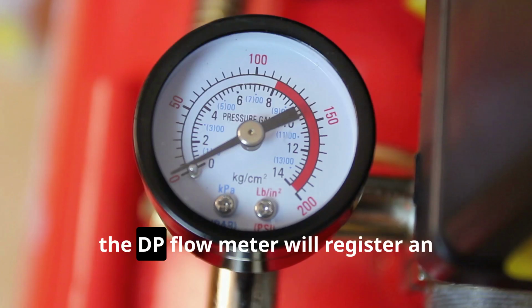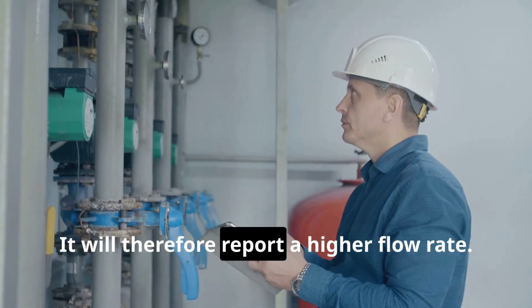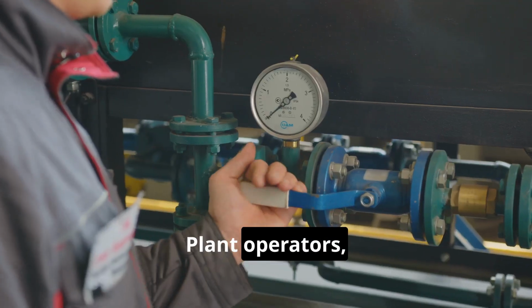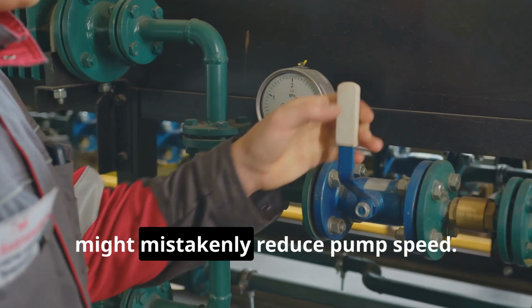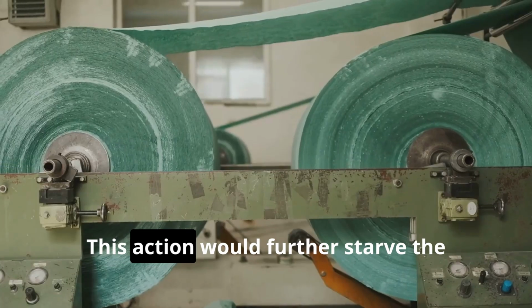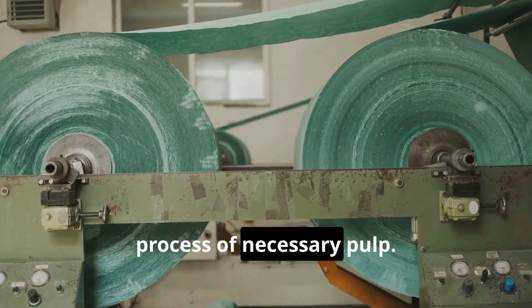However, the DP flow meter will register an increased pressure drop. It will therefore report a higher flow rate. Plant operators, seeing this high reading, might mistakenly reduce pump speed. This action would further starve the process of necessary pulp.